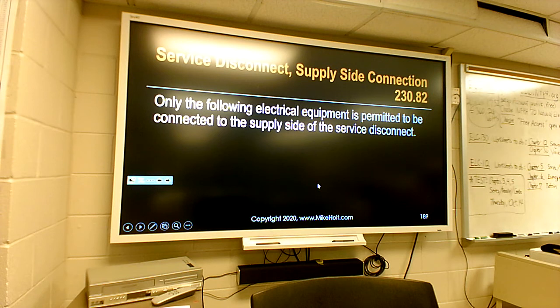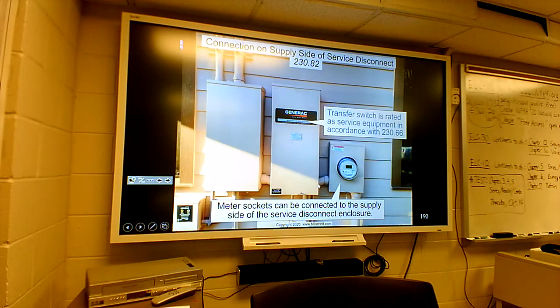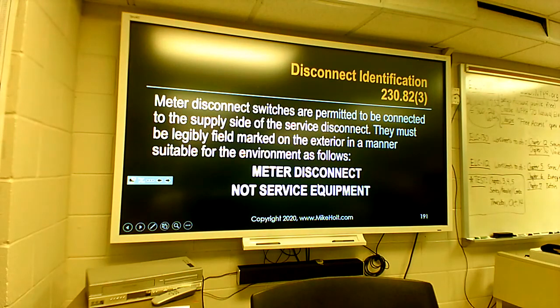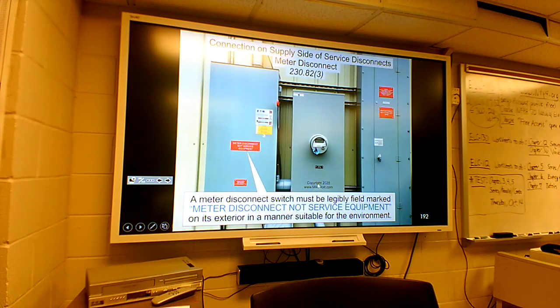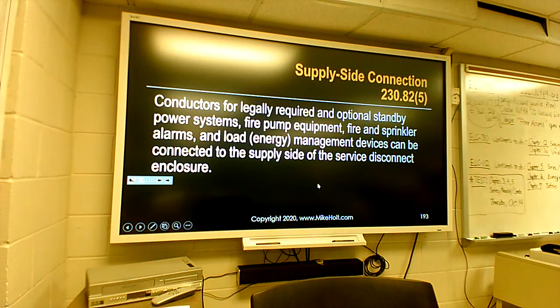Only the following electrical equipment is permitted to be connected to the supply side of your service: transfer switch, meter sockets, and they must be labeled. A meter disconnect switch must be field marked. This is a meter disconnect, not service equipment. Conductors for legally required and optional standby power systems, fire pump equipment, fire and sprinkler alarms, and load (energy) management devices can be connected to the supply side of your service disconnect.